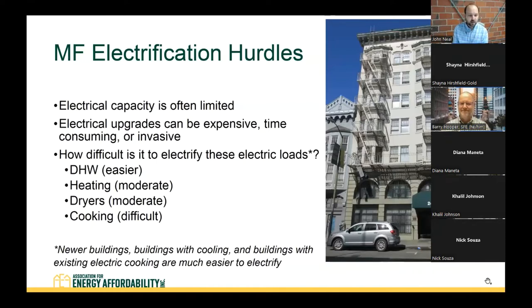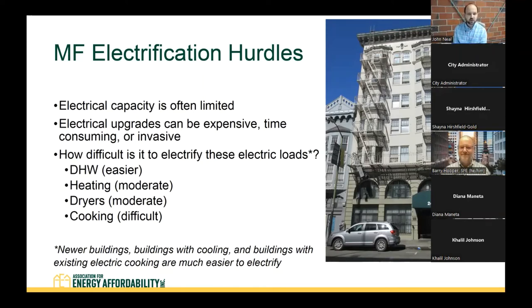Multifamily buildings, especially in the mild Bay Area climate, tend to have minimal existing electrical capacity. Making electrical upgrades to support full electrification can be expensive and time-consuming, so we try to find ways to work within the existing electrical service size. This is on a continuum: if a building is newer, has electric cooking or cooling, the odds of fully electrifying without triggering a service upgrade increase. But if you have all-gas end uses for domestic hot water, heating, cooking, etc., the odds of avoiding a service upgrade are lower.